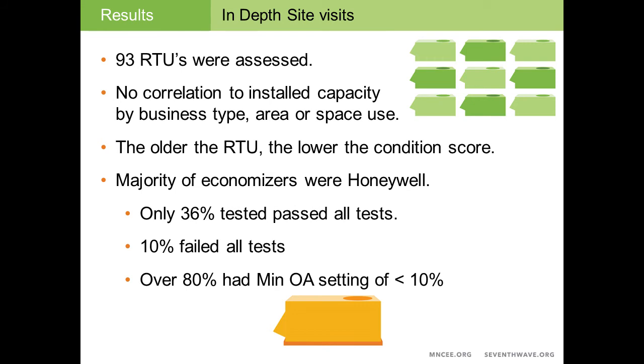There was no correlation that we could find between the capacity of the business type or the area or the space use. And it wasn't a statistically significant sample. It was just the ability to go and get an in-depth site visit from these sites that were a subset of the characterization grouping. There's no shock here, but what we found is that the older the RTU, the lower the condition score is, or the worse the condition of the rooftop unit is. The roof is a very harsh environment. It is extremely hot in the summer, and in the state of Minnesota, it gets extremely cold in the winter. So rooftops do take a beating, and the older they get, the more beat up and the lower condition score they got.